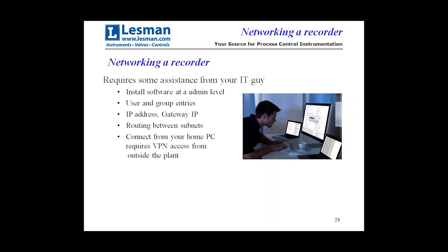The other part is networking the recorder. You've got to use your IT guy just like you would for anything else. It involves installing software at an administrative level, sometimes setting up user and group names. Typically he assigns an IP address and knows the gateway IP address to route between subnets. If you want to connect from home with a PC, he can set up a VPN so you can get in from wherever. Involve your IT guy in this and everybody's happy.